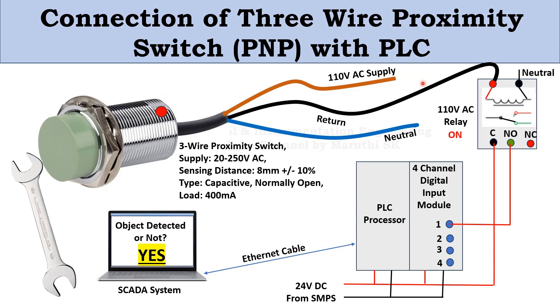In the 2-wire system, if the relay coil breaks down, the proximity switch will not work. The advantage of the 3-wire proximity switch is that we have separately applied 110V AC and neutral. Even if the relay coil breaks down, the proximity switch itself will still work and give a signal through the black wire — though the signal won't reach the relay if the cable has broken.